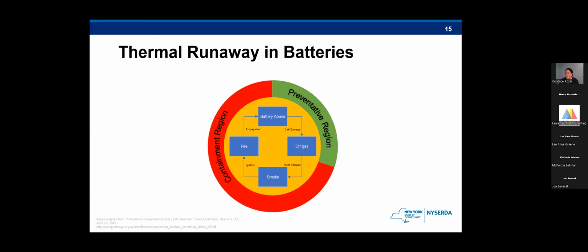So energy storage systems have to have a device that can recognize when the temperature is rising. And this device, which is usually the battery management system, should isolate that area and send a signal to the owner of the system that there's currently a problem. When there is battery abuse or off-gassing, there's still time to prevent the spread of thermal runaway. But usually once smoke or fire is visible, a thermal runaway event is underway and it will need to be contained.